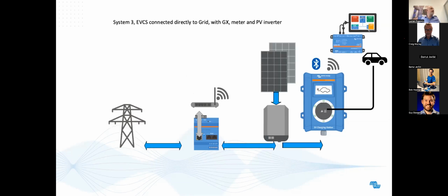The next system type has the EV charging station connected directly to the grid, but also a PV inverter is added. By doing so, you can have automatic mode - the charging station will charge with the excess power that the PV inverter is pushing into the grid, so only that amount will be used for charging. If you are producing less than the minimum current, the charging station will stop.